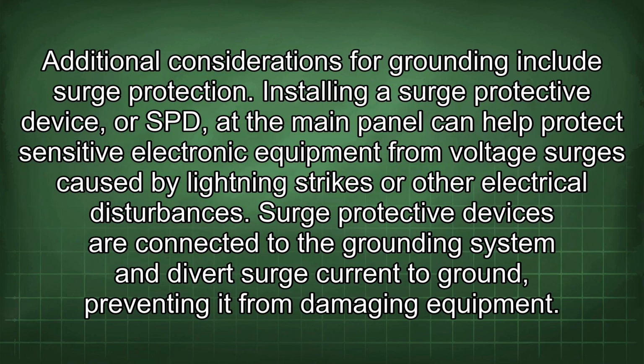Additional considerations for grounding include surge protection. Installing a surge protective device, or SPD, at the main panel can help protect sensitive electronic equipment from voltage surges caused by lightning strikes or other electrical disturbances. Surge protective devices are connected to the grounding system and divert surge current to ground, preventing it from damaging equipment.